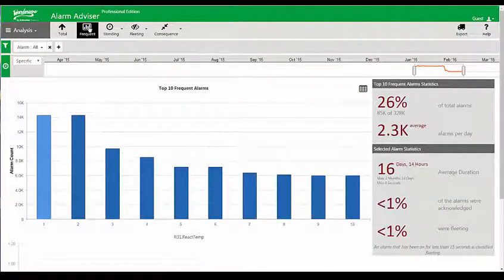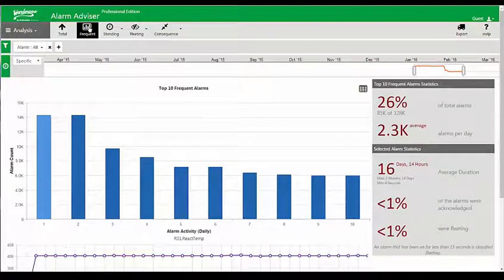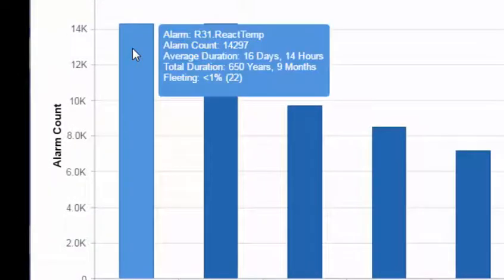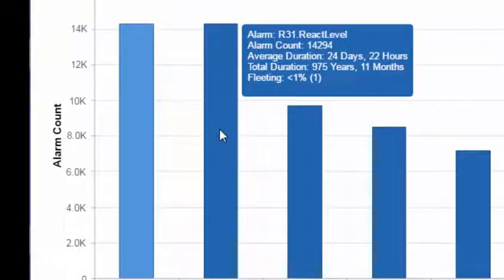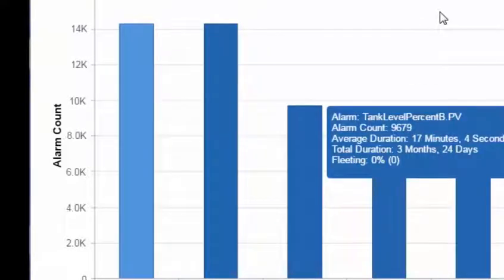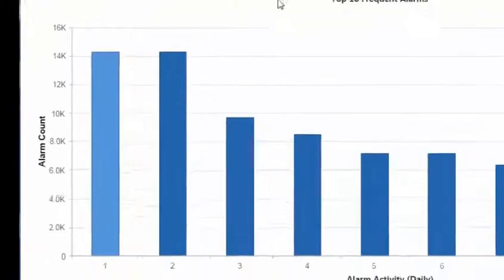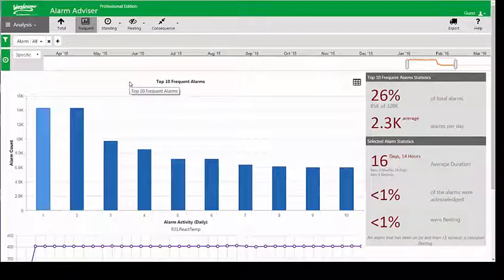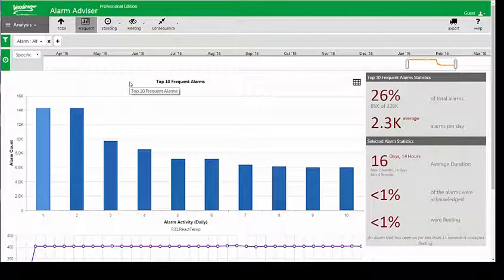This next tool shows the frequency of alarms, and I think this is the most useful tool in the toolbox. It gives me an understanding of what alarms are causing problems — I can hover over a specific alarm and it tells me the name and how many times it has occurred. So I can go out and fix that alarm, understand what's going on, fix that instrument, add a debounce timer, or inhibit that alarm during certain process conditions so I'm not overloading my operators with nuisance alarms.